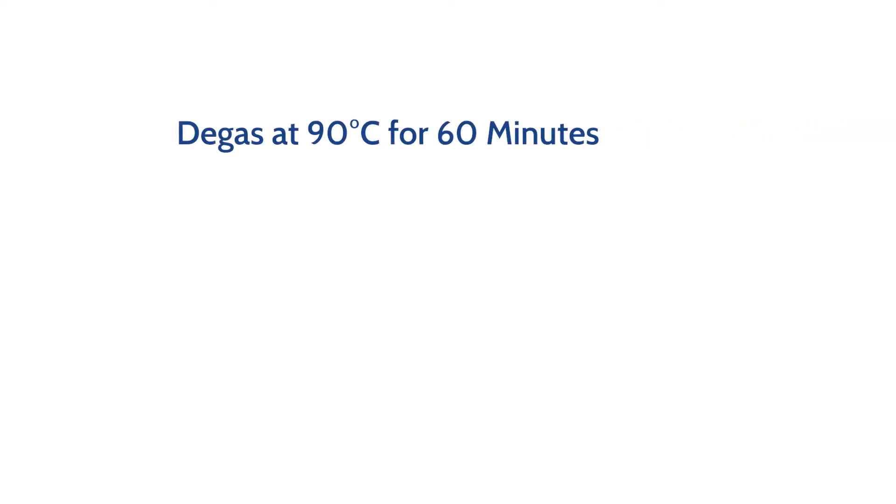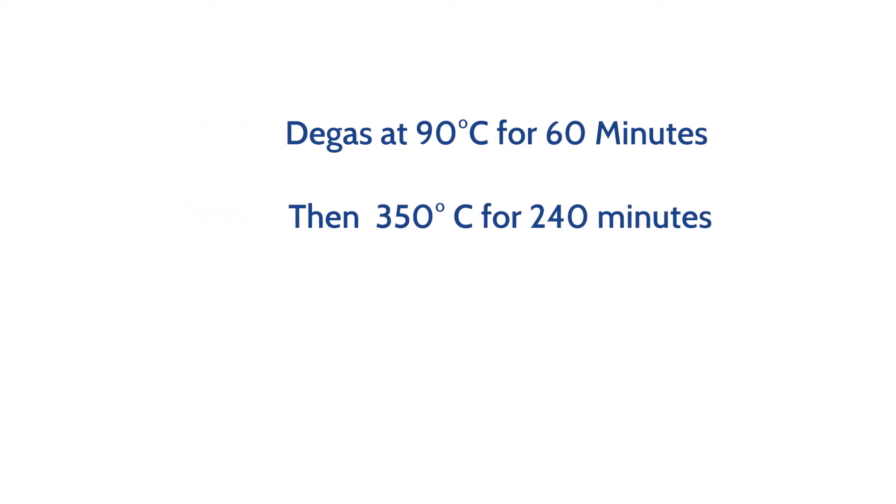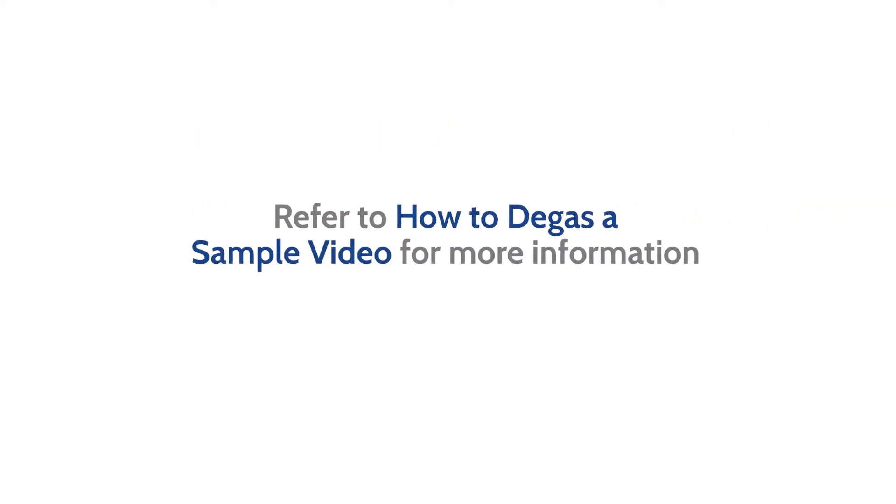Degas at 90 degrees Celsius for 60 minutes and then 350 degrees Celsius for a minimum of 240 minutes. Please refer to How to Degas a Sample video for more information.